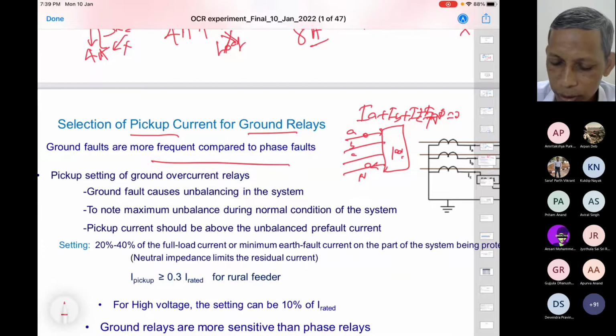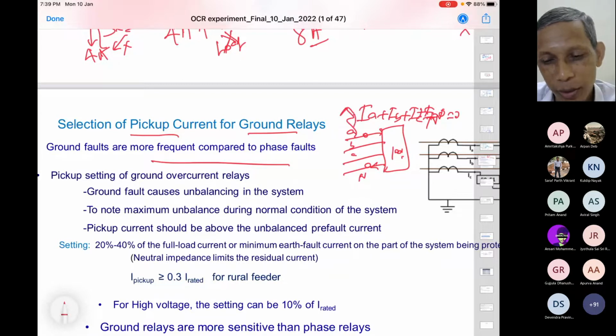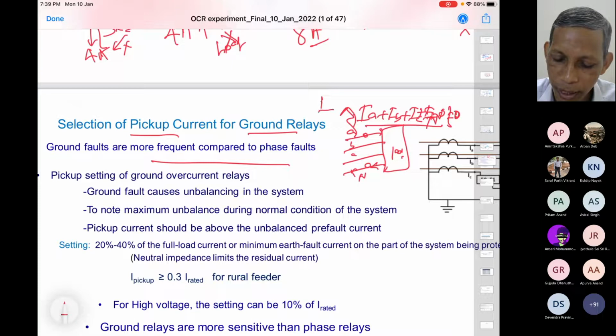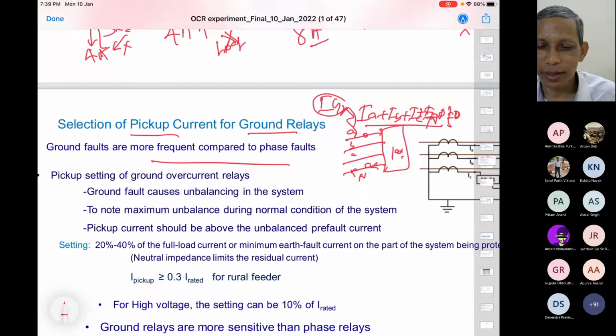But when you talk about the fault, it is not to consider neutral current. This current goes to the ground, to the neutral earthing part of the transformer, not this neutral, to follow the distribution. So therefore, when you consider this part, it will now be non-zero. Agree? So this is nothing but Ig. Ig is normally 0 ideally, but some leakage current will be there, from the cable perspective, so leakage current only. That becomes very small. Agree?